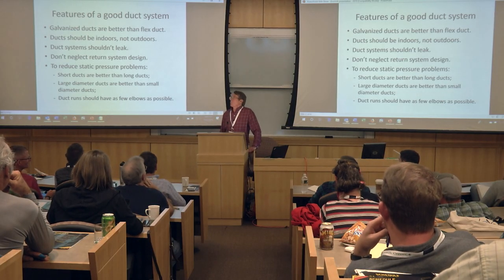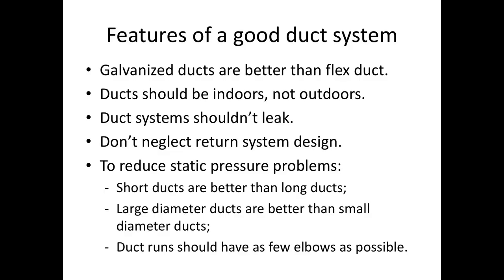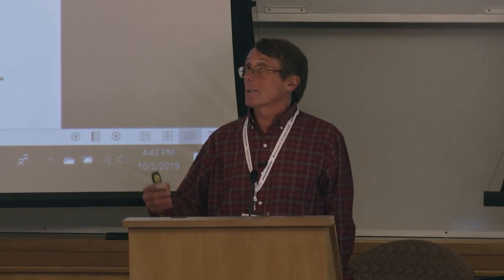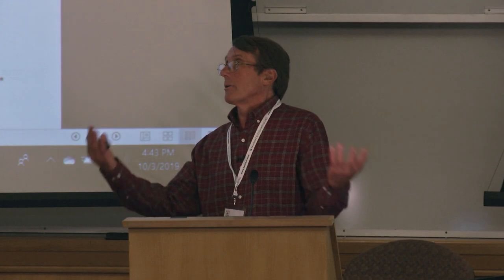High velocity duct systems can work, but you take an energy efficiency hit. The ideal duct system is oversized—you want big, fat ducts that let air easily get where it's going, and as few elbows as possible. Length, small diameter, and elbows all introduce static pressure, and that static pressure is only overcome by the fan. If you need a high power fan to overcome a small diameter duct or a system with a lot of elbows, your energy costs go up as more energy is devoted to distribution. A big fat fan motor in your basement isn't a huge penalty in winter, since the hot motor at least adds some heat to the house. But in an air conditioning system, that hot motor adds to your cooling load, giving you a double whammy in the cooling season. So I'm not a fan of these high velocity, tiny diameter ducts—you really want to design for minimum static.